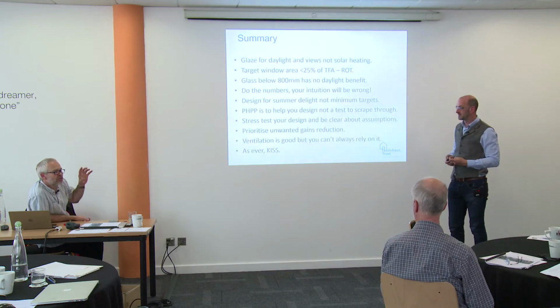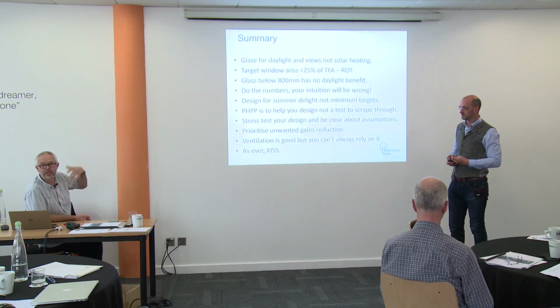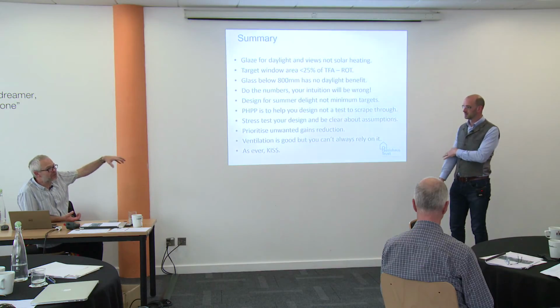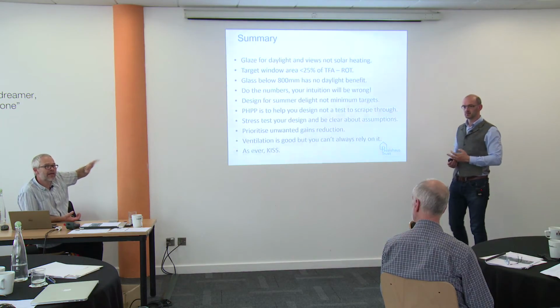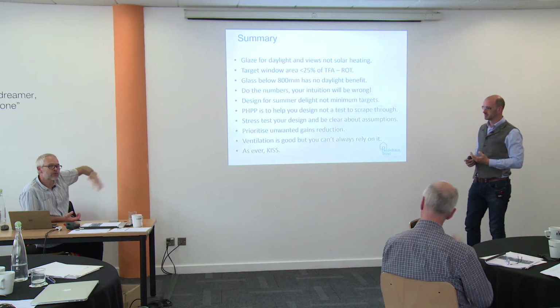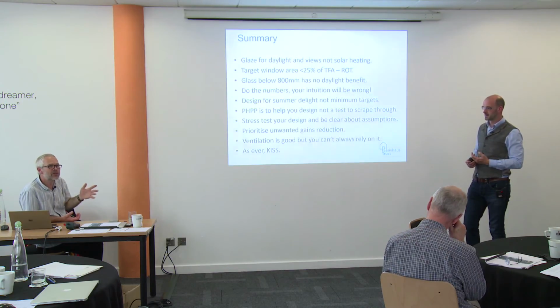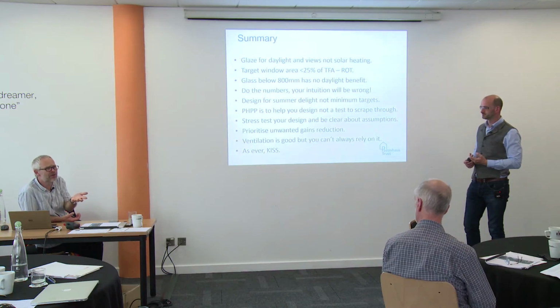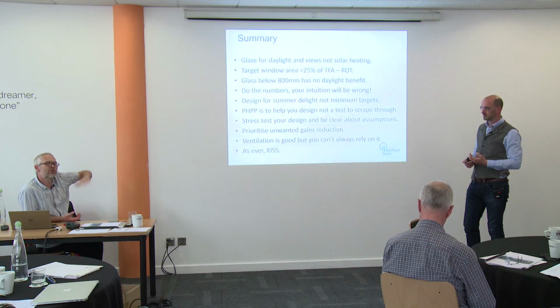One thing on the schools: the original assumption was, particularly because schools have bigger fans and more power, we specifically designed to run with window opening and turn the MVHR off in summer, so we had a separate fan for the loos. We really spent some effort to make it so in summer you turn it off and work with window opening, with automatic openers. Complete disaster, because they were miserable. Summer suddenly turns into miserable weather with a cold wind and the windows are all shut, and the CO2 levels in the classrooms went up with the post-occupancy monitoring. Stuffy conditions, really not good.